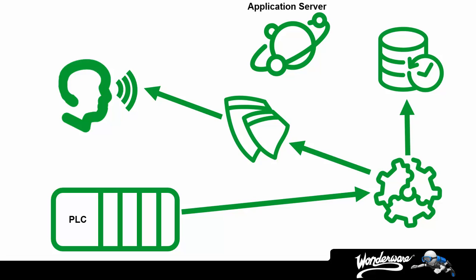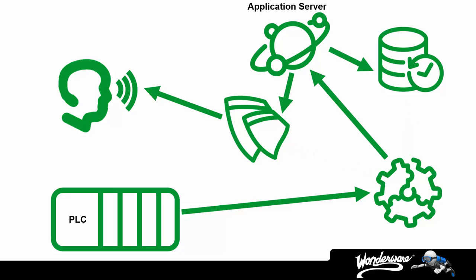For example, instead of defining all the data points you need to visualize within the HMI and then doing it all over again in the historian product, application server software defines all the PLC points that both are going to need, and it automatically configures the historian for you. It can even provide graphics for the HMI with all the links and animations already predefined, greatly simplifying the HMI application. It does much more than this, but for the purpose of our licensing discussion, this will have to suffice.